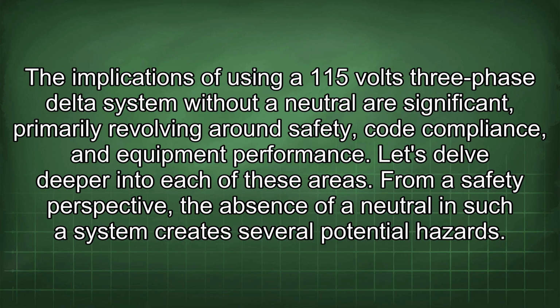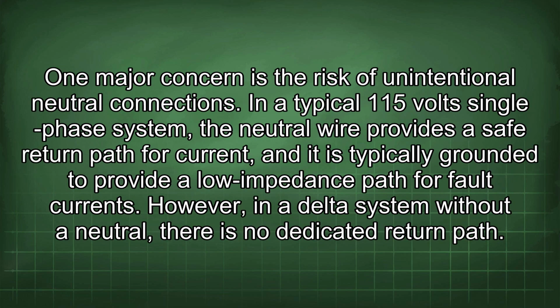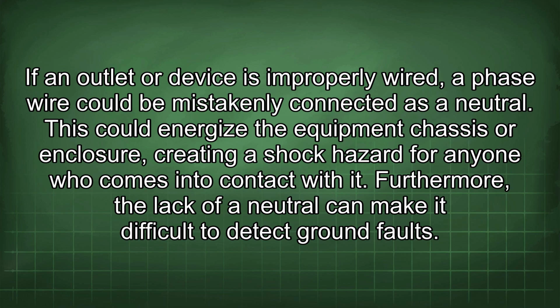From a safety perspective, the absence of a neutral in such a system creates several potential hazards. One major concern is the risk of unintentional neutral connections. In the typical 115 volt single-phase system, the neutral wire provides a safe return path for current, and it is typically grounded to provide a low impedance path for fault currents. However, in a delta system without a neutral, there is no dedicated return path. If an outlet or device is improperly wired, a phase wire could be mistakenly connected as a neutral. This could energize the equipment chassis or enclosure, creating a shock hazard for anyone who comes into contact with it.